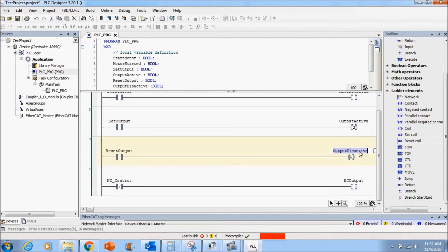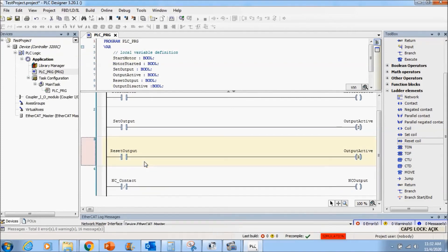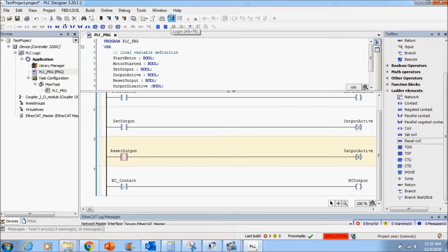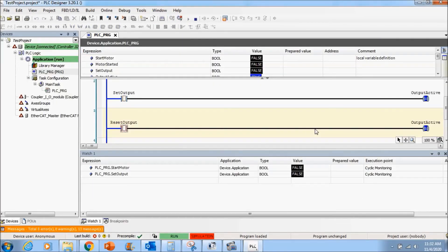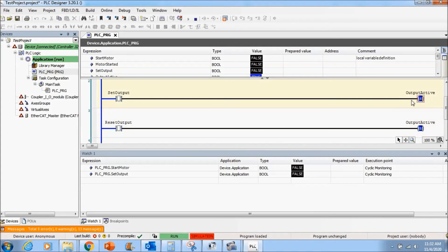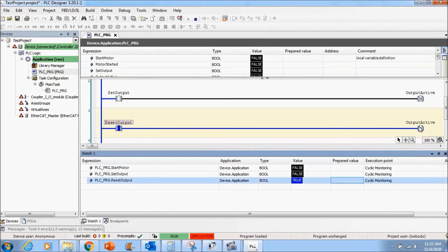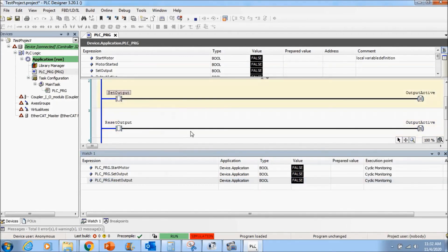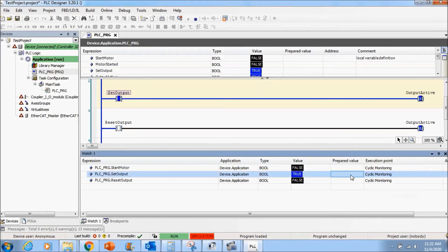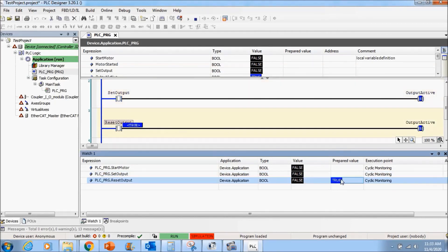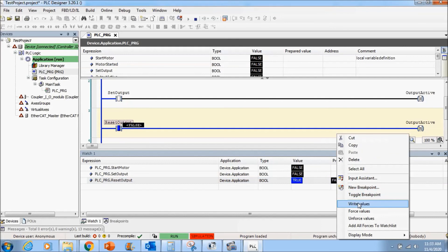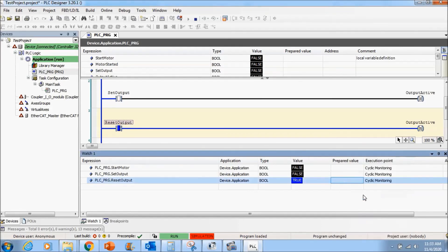How can we reset it? We can reset the output. Let's go offline — output active will be reset with this contact. Login again with online change and run simulation. Now you can see output is still active. If I activate reset output to true, output active is reset. Let's make it false, then set output true again — it is set. Make it false — still remains set. When reset output becomes true, output active is reset. This is how we use set and reset instructions in Lenze PLCs.